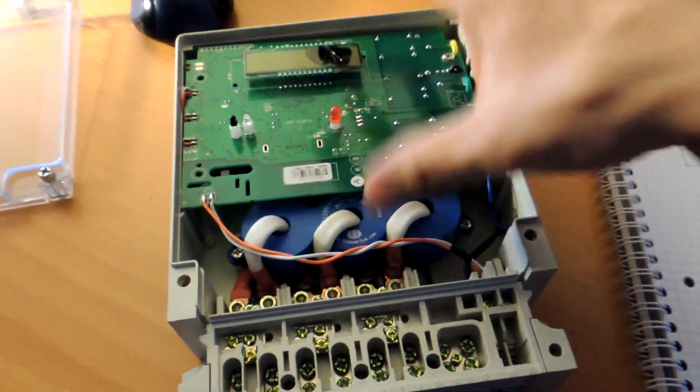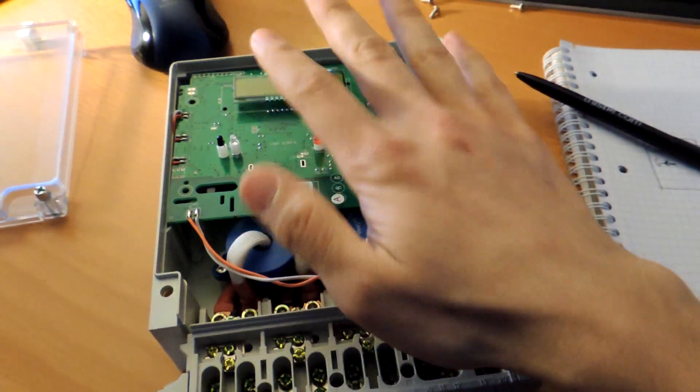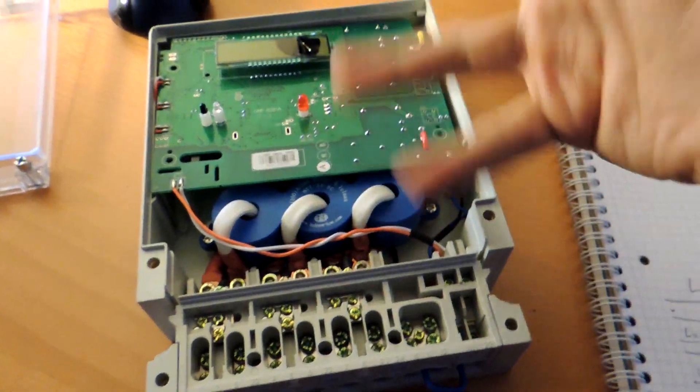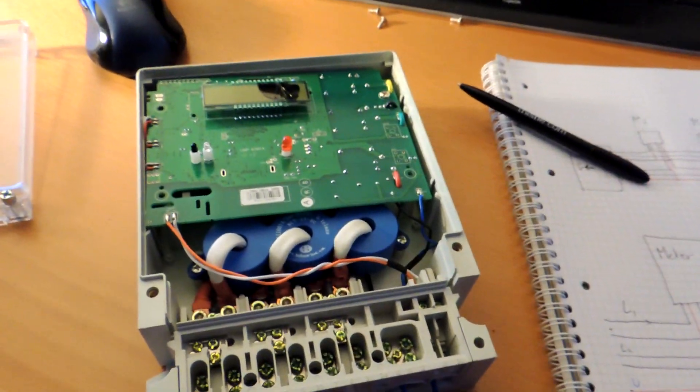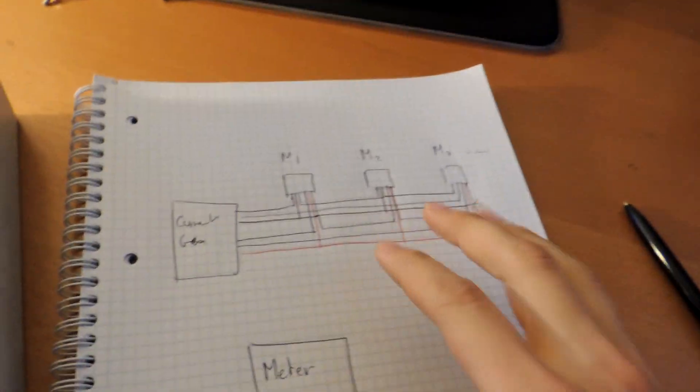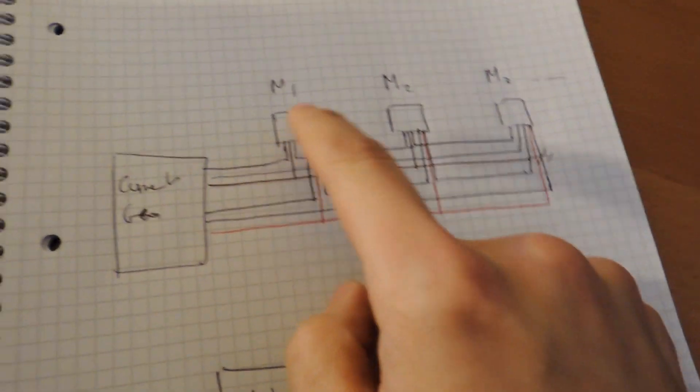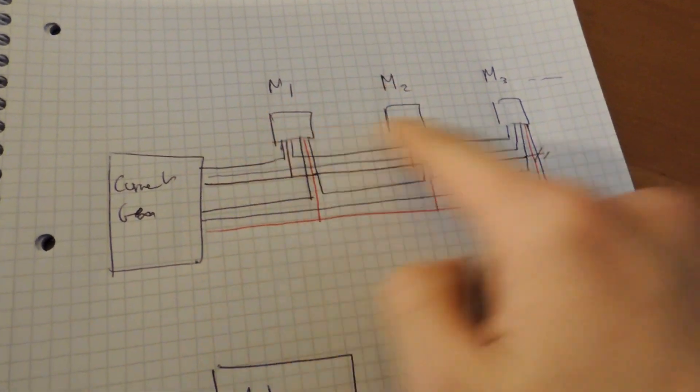So each year they take meters and they put them on the calibration bench to test them with reactive currents, all sorts of currents. So what they do here, I've got the bench there, so the meters are in series.